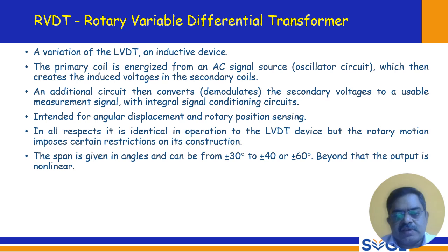The span is given in angles and can be measured plus or minus 30 degrees to plus or minus 40, or even 60. Beyond that, output is non-linear. So up to plus or minus 60 degrees, it is the best suited device.